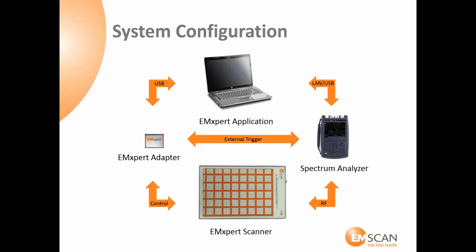So we've just seen the array of sensors. The way this works in a system is that the array is actually a passive array. There are 1,200 probes arranged in a grid over the surface, and those probes simply couple the energy and feed it into a spectrum analyzer. The spectrum analyzer is connected to a computer where you'll run the EMXpert software. There's also a small adapter that synchronizes the switching of the probes and the triggering of the spectrum analyzer. So the combination of this system is essentially what does the entire near-field measurement.